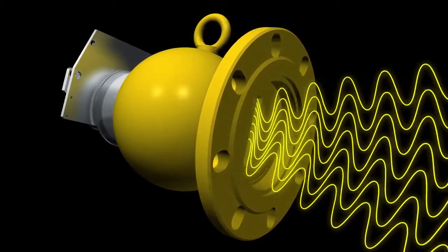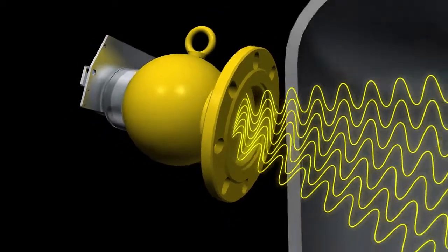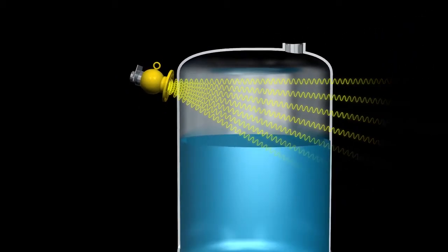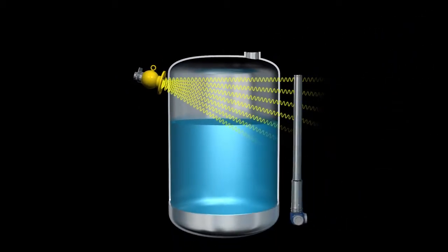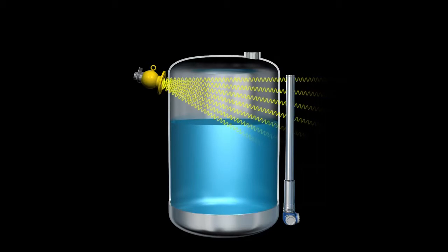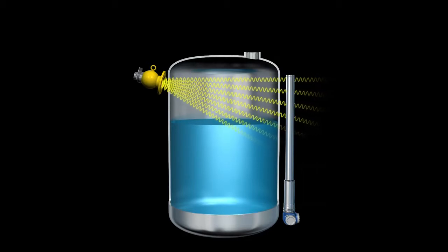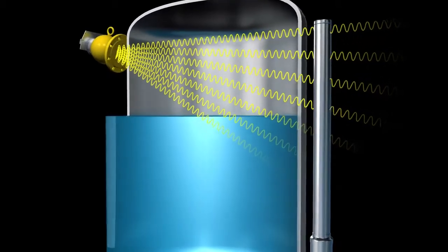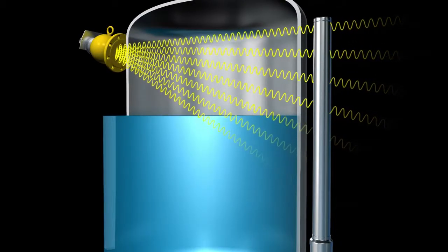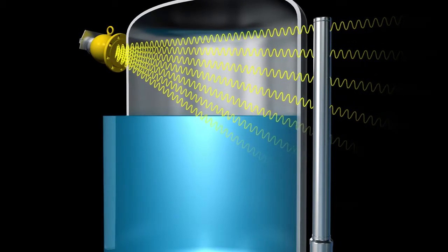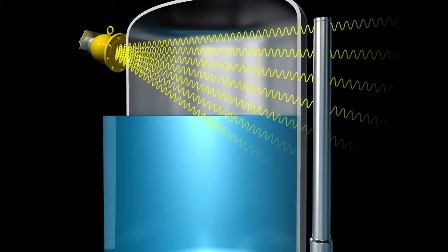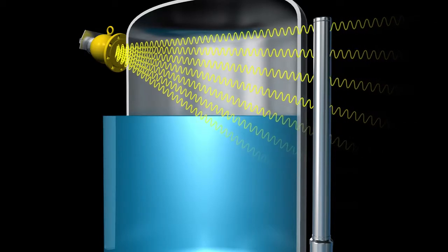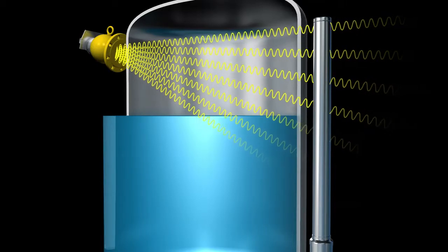The source container is arranged on one side of the tank. On the opposite side, the compact transmitter is located to detect the radiation. This gamma radiation is used to radiate through tanks and pipelines from outside. As materials are penetrated, the radiation is attenuated by the density of the medium and the material thickness. The emitted gamma radiation is detected by the compact transmitter.